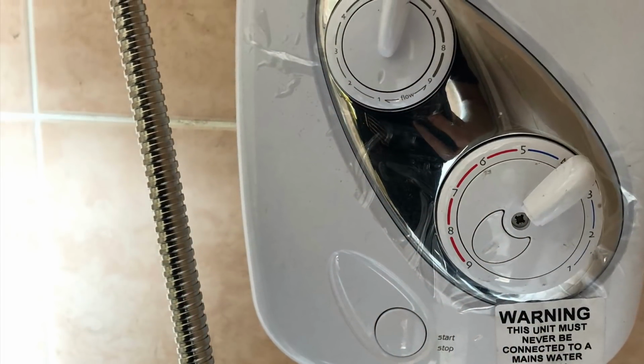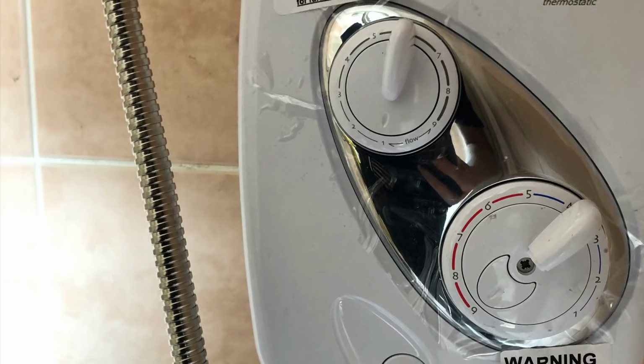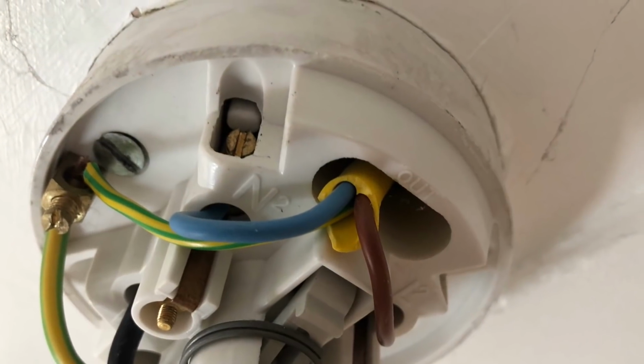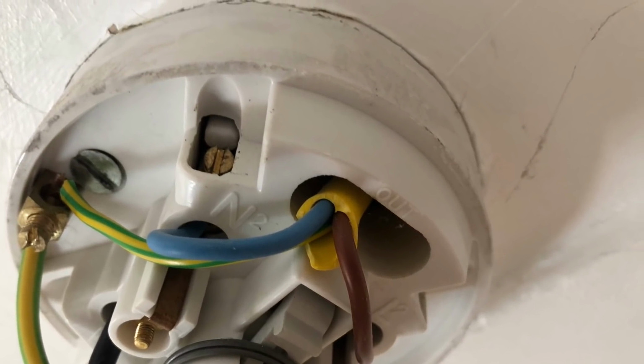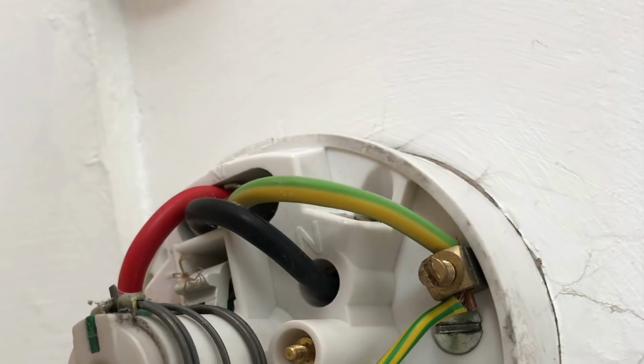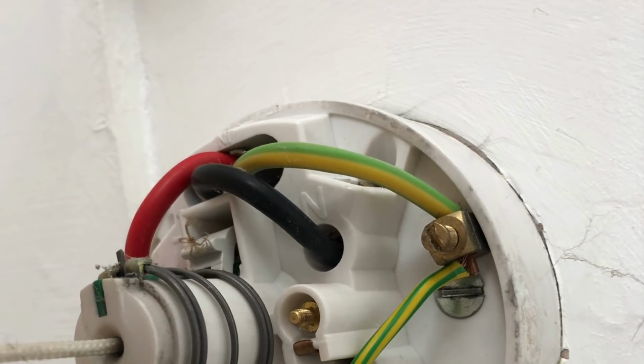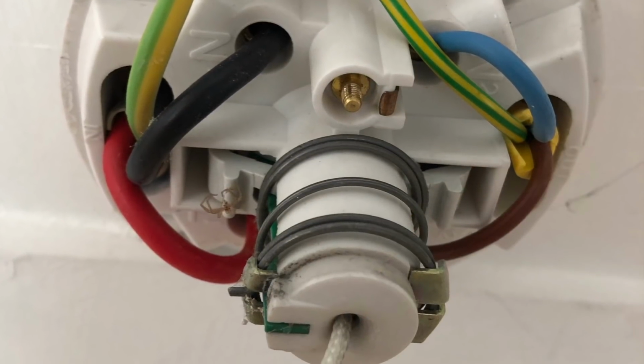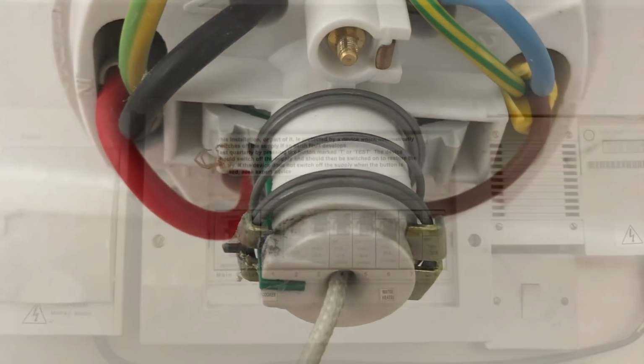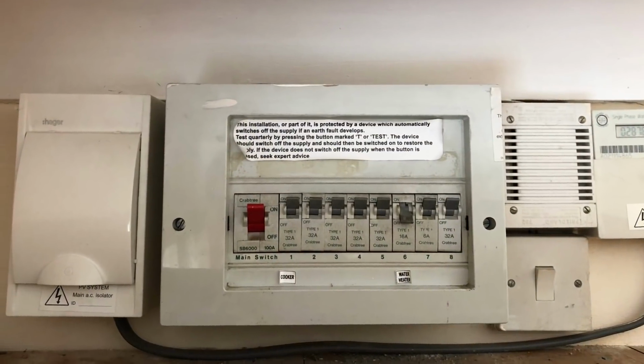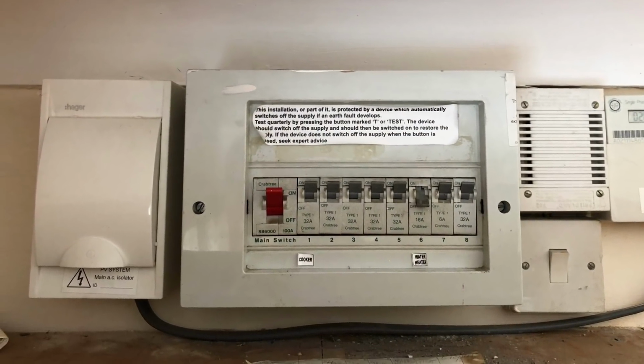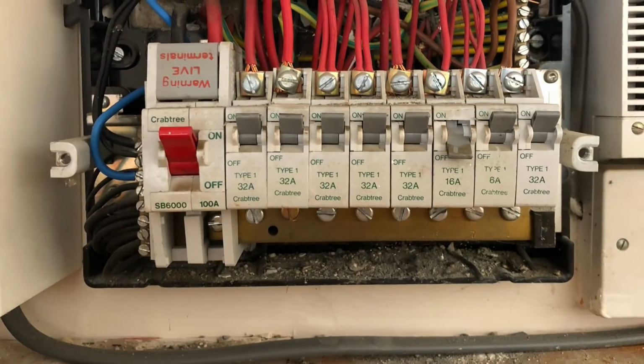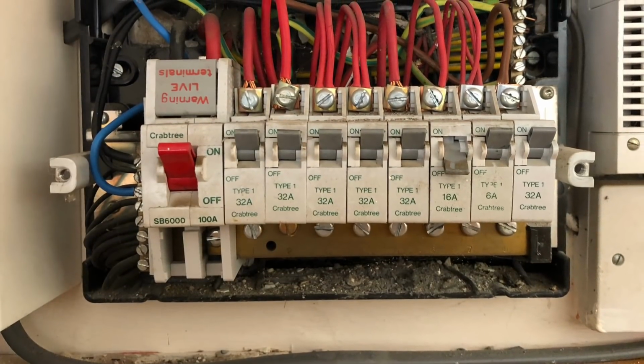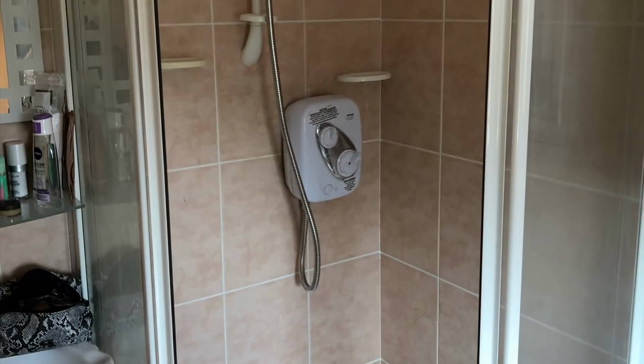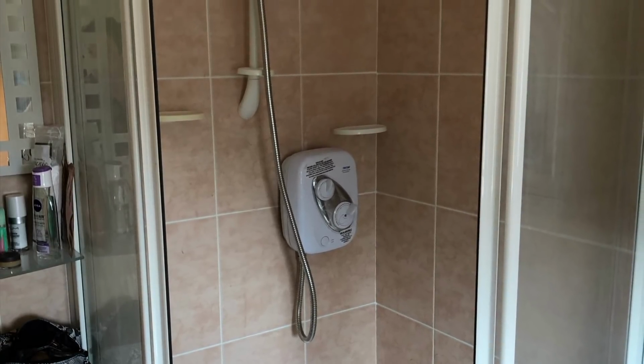So here's the shower, as you can see, brand new, plastic film still on, and here's the isolator switch with the yellow flex going out of it and a 6mm twin and earth cable coming in to supply it. All very bizarre because the incoming cable had no power to it. Here's the consumer unit, and although there was one circuit that was turned off, which has water heater, it was actually nothing to do with that, it was just the immersion heater. And all the power was outgoing.